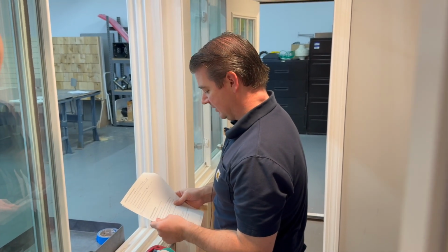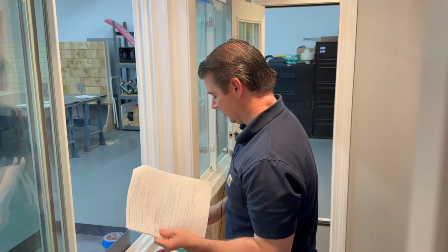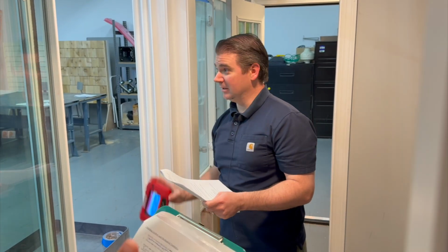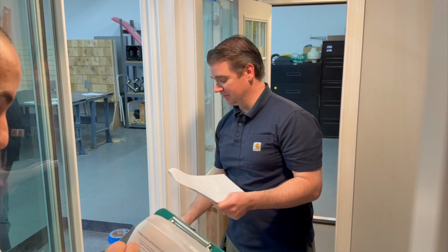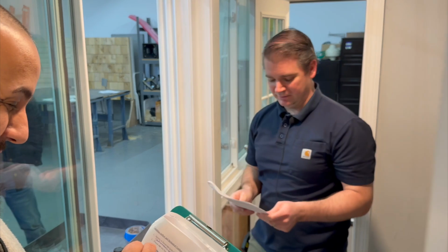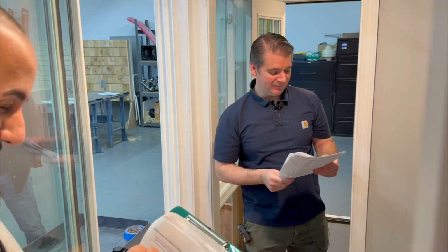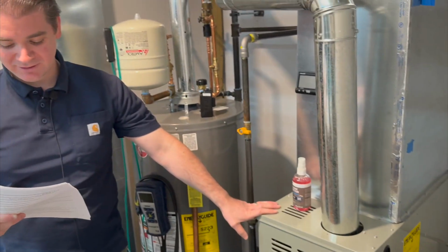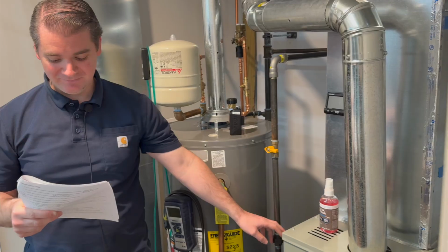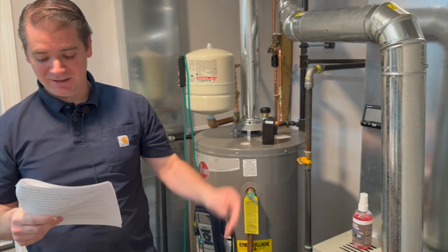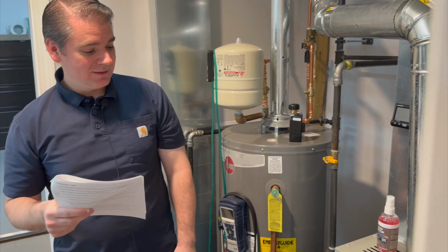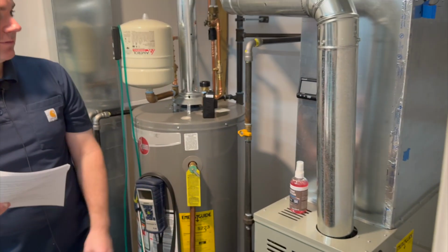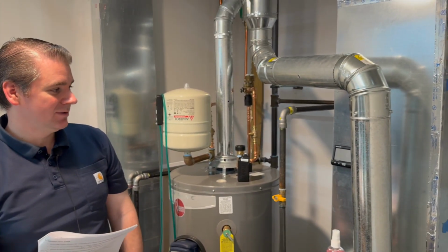Now we're on to the heating, cooling, and domestic hot water equipment. And it makes it easier, right? My manometer is already turned on, so I don't have to worry about that later. Identify the basic heating or cooling system type, fuel, distribution, venting. So this is a forced warm air furnace, natural gas. It's ducted, obviously, if it's a furnace. And venting, it's an induced draft fan, atmospherically vented.